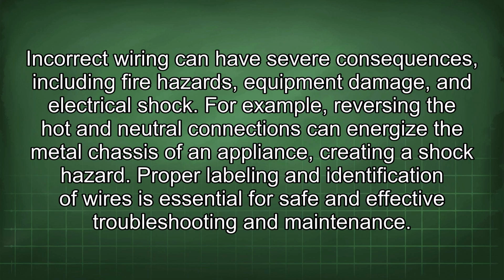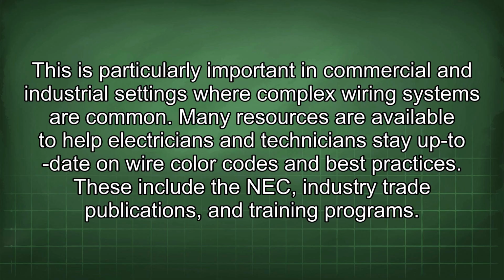Incorrect wiring can have severe consequences, including fire hazards, equipment damage, and electrical shock. For example, reversing the hot and neutral connections can energize the metal chassis of an appliance, creating a shock hazard. Proper labeling and identification of wires is essential for safe and effective troubleshooting and maintenance. This is particularly important in commercial and industrial settings where complex wiring systems are common.